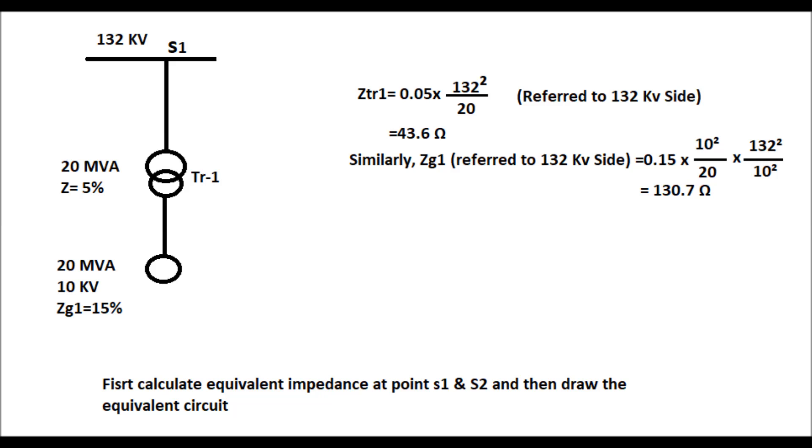Similarly, ZG1 that is referred to 132 kV side will be equal to 0.15 times 10 squared by 20 times 132 squared by 10 squared. That will come to 130.7 ohm.